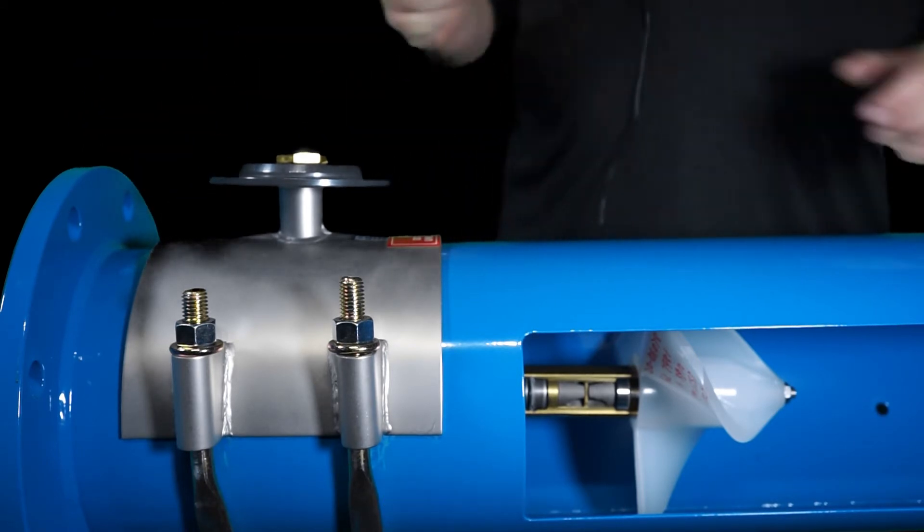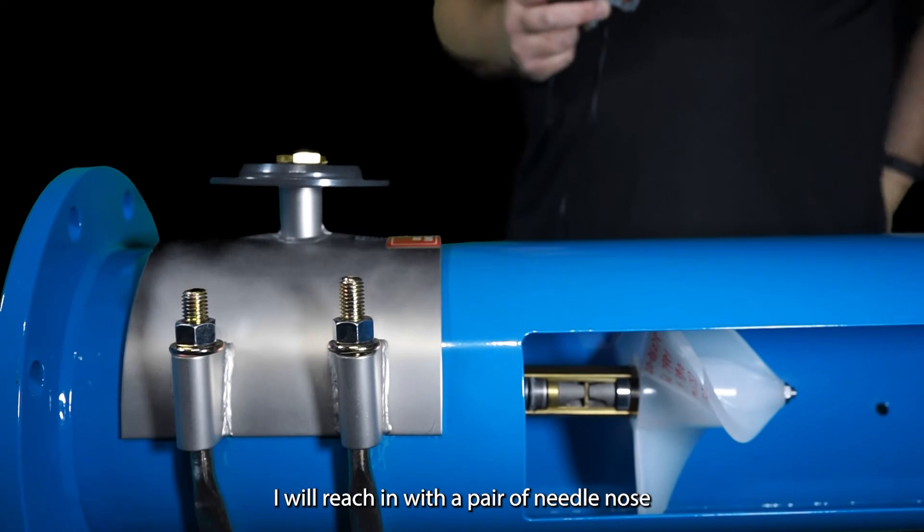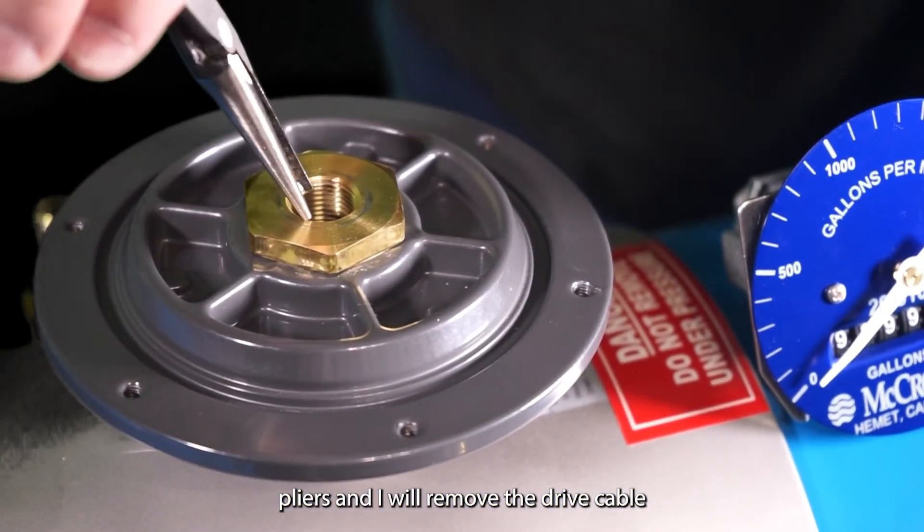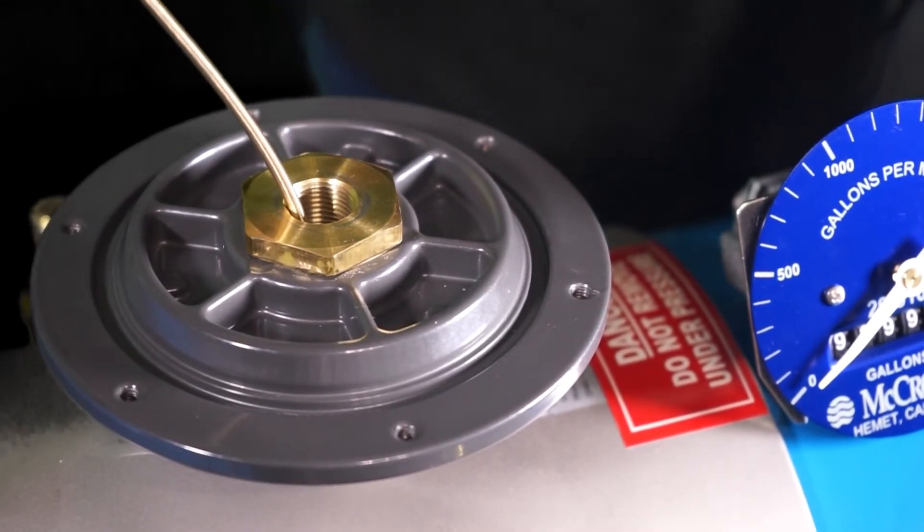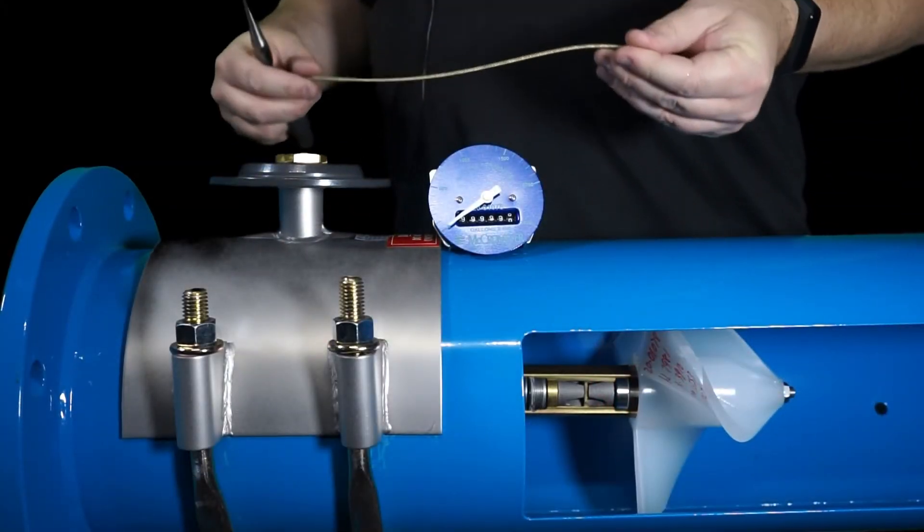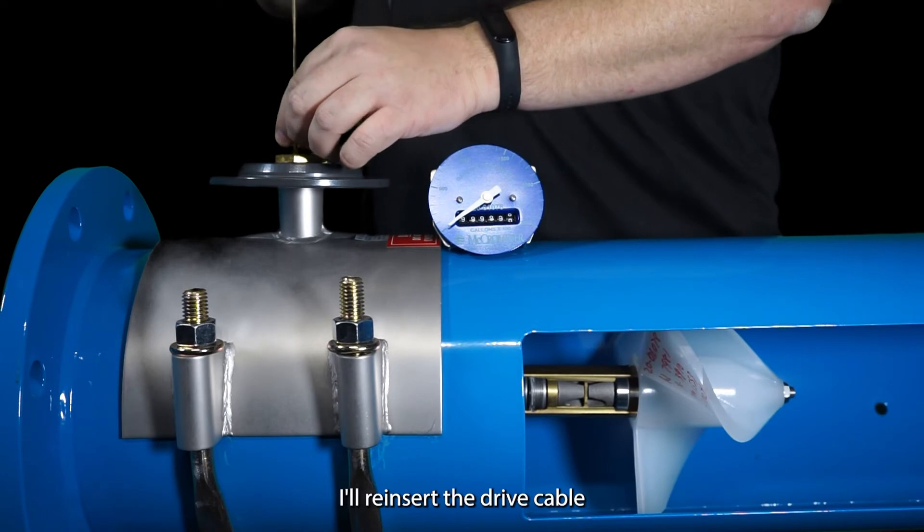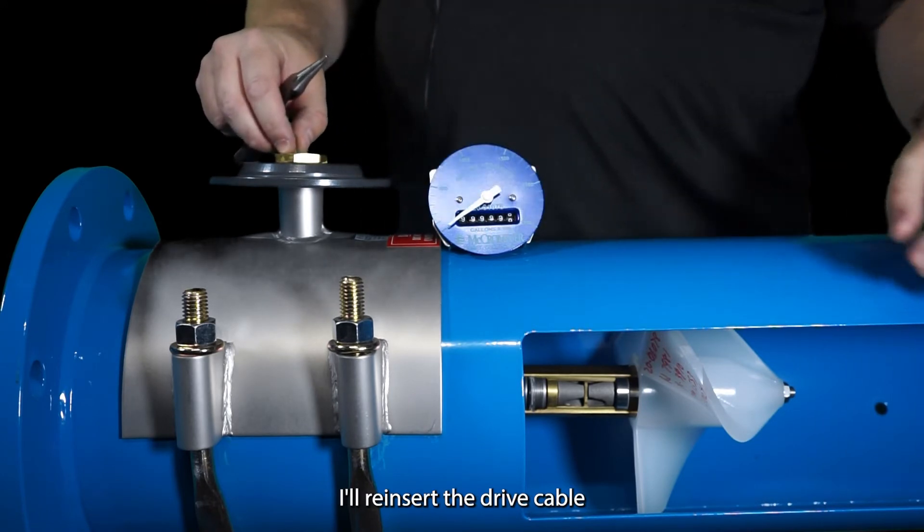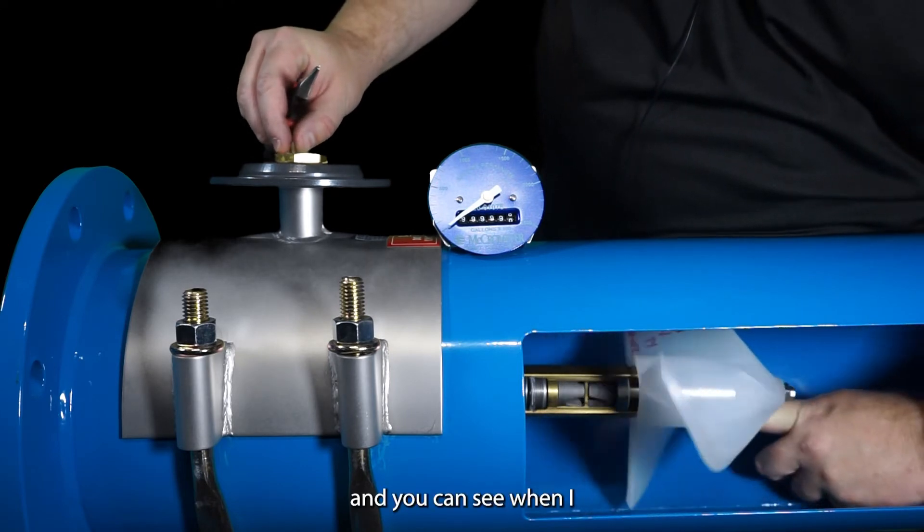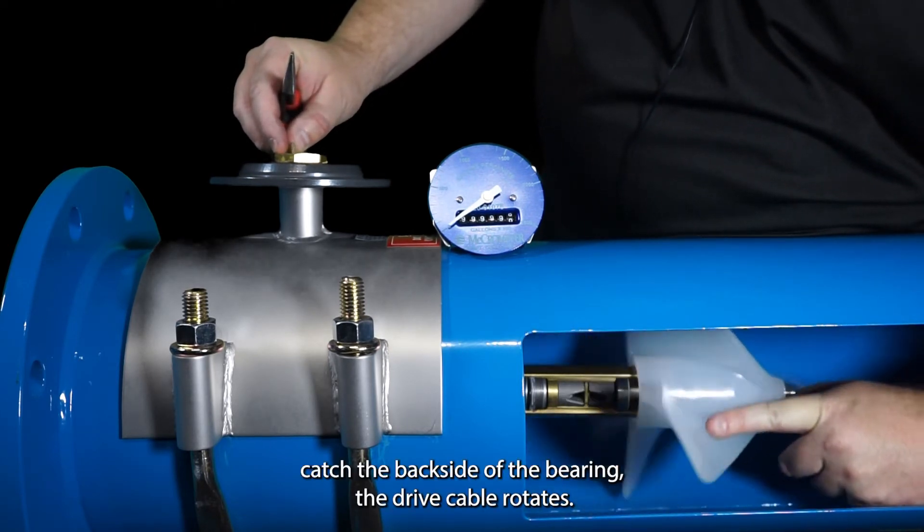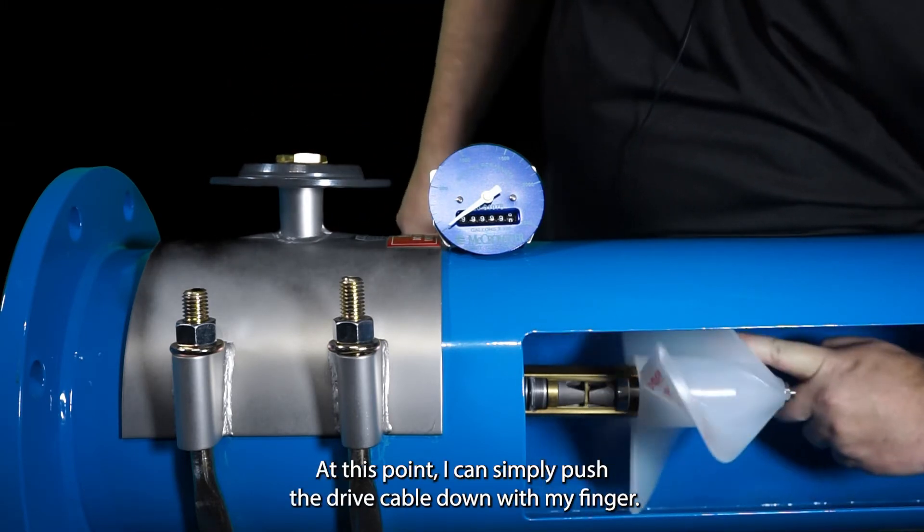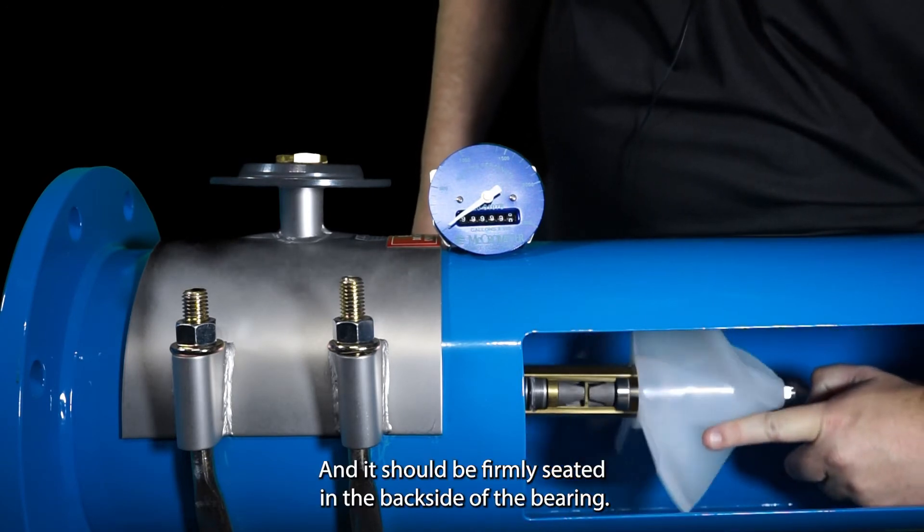So to check that I will reach in with a pair of needle nose pliers and I'll remove the drive cable and quickly inspect it. If everything looks good I'll reinsert the drive cable until it catches and you can see when I catch the back side of the bearing the drive cable rotates. At this point I can simply push the drive cable down with my finger and it should be firmly seated in the back side of the bearing.